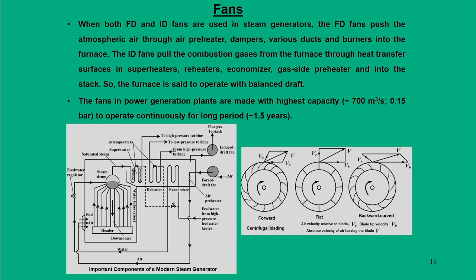In a balanced draft steam generating unit, both a forced draft fan and an induced draft fan are used. They operate such that the system is under balanced draft — the forced draft fan pushes air and the induced draft fan pulls combustion products out of the system. For large power generating plants, a typical fan handles about 700 cubic meters per second — a very high volume flow rate but at a very low pressure differential of about 0.15 bar. Since the plant runs continuously, these fans run 24/7 and their life period is about 1.5 years.